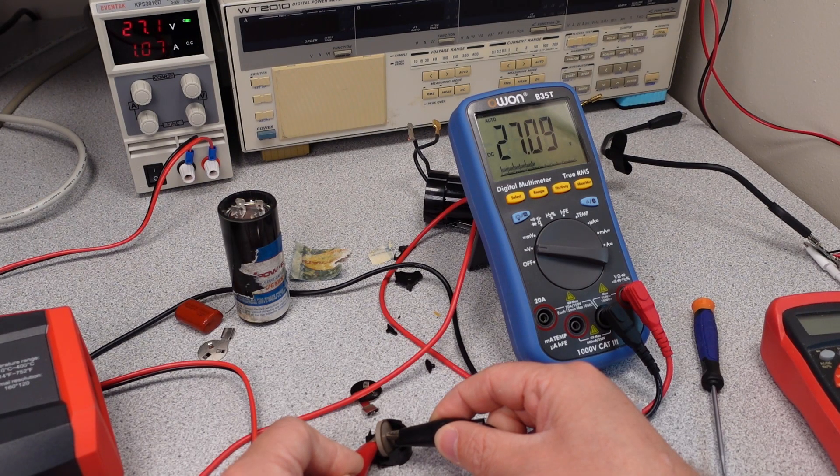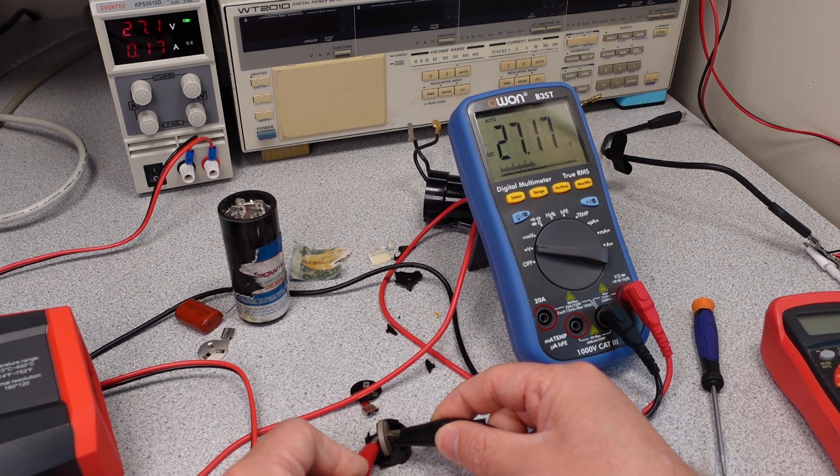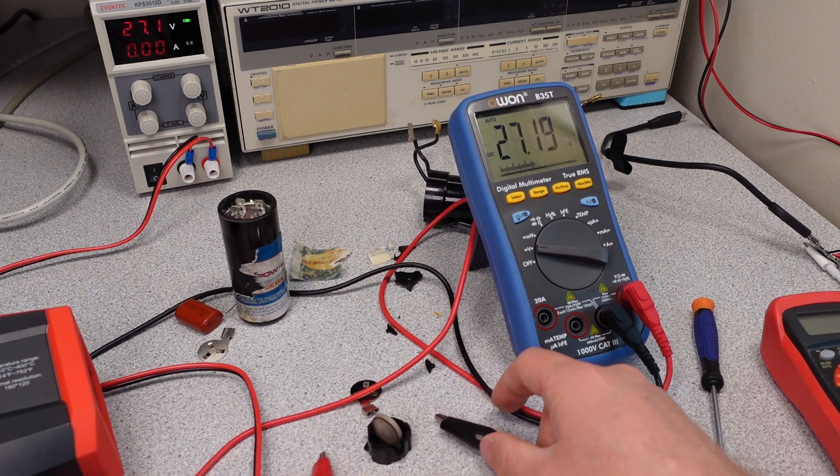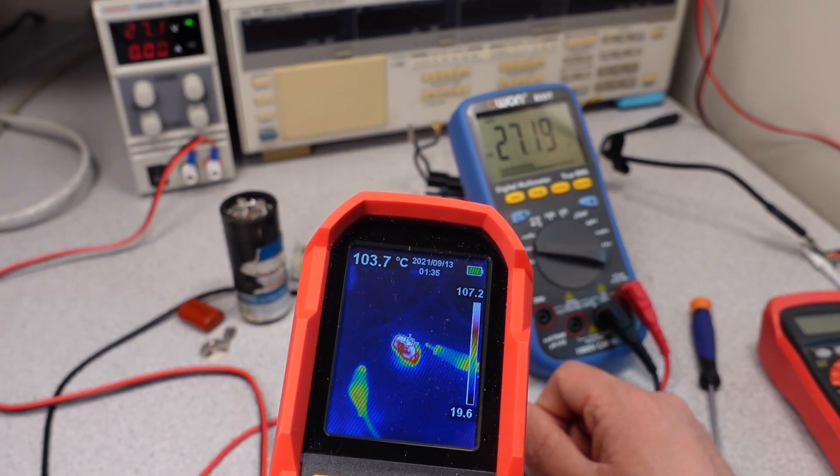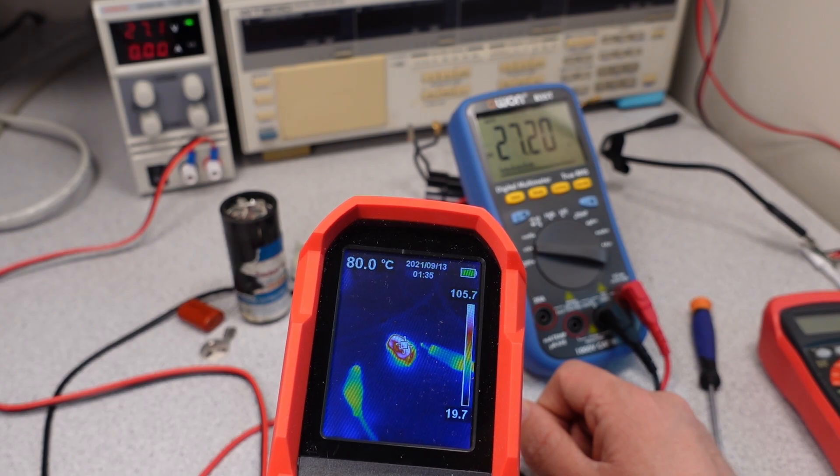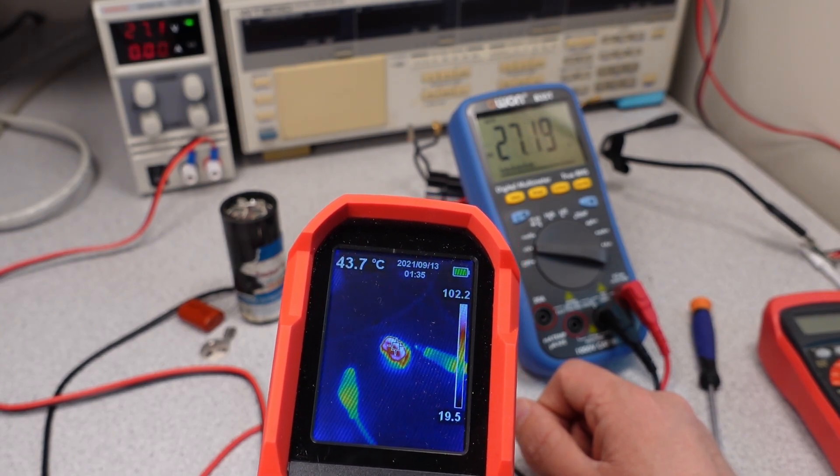So we're drawing about 1 amp right now. What I'm expecting to see is the current start to drop. And take a look at that. The current dropped right down to almost zero amps now. And what we should see is this thing's hot. And there it is. You can see we're about 106, 107 degrees C. So if we cool that back off, we should see a high current. And we'll watch that again.